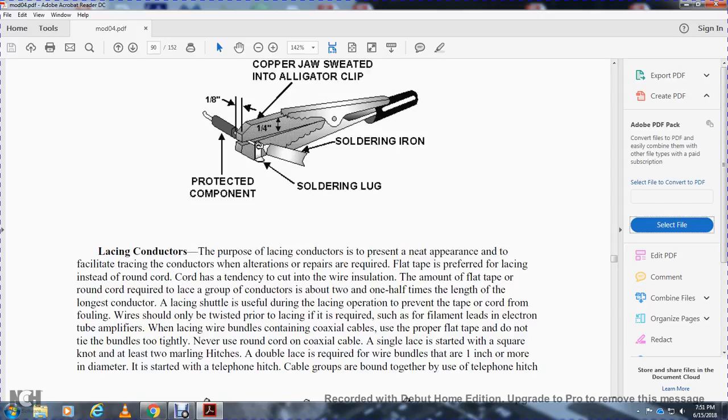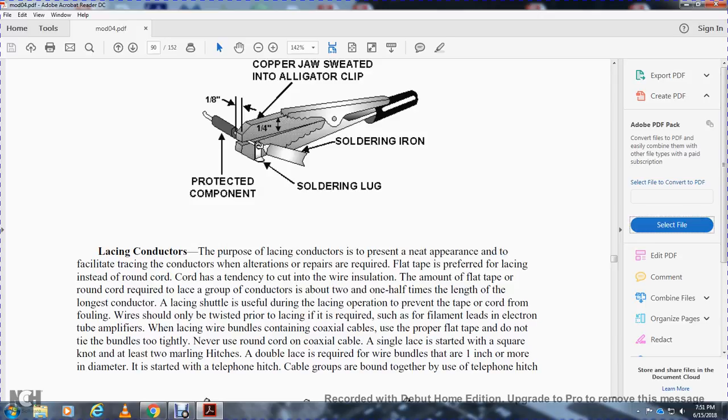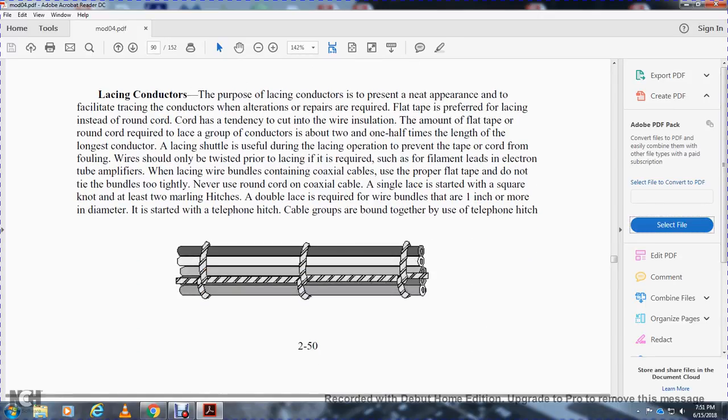Lacing conductors. The purpose of lacing conductors is to present a neat appearance and facilitate tracing of the conductors when alterations or repairs are required. Flat tape is preferred for lacing instead of round cord. Cord has a tendency to cut into the wire insulation. The amount of flat tape or round cord required to lace a group of conductors is about two and a half times the length of the longest conductor in the harness. A lacing shuttle is useful during the lacing operation to prevent the tape or cord from fouling. Wires should only be twisted prior to lacing if it is required, such as filament leads to electron tube amplifiers. When lacing wire bundles with containing coaxial cables, use proper flat tape. Do not tie bundles too tight and never use round cord on coaxial cable. Single lace is started with a square knot using at least two marlin hitches. Double lace is required with wiring bundles that have one inch or more in diameter. It is started with a clove hitch. Cable groups are bound together with the use of the clove hitch.